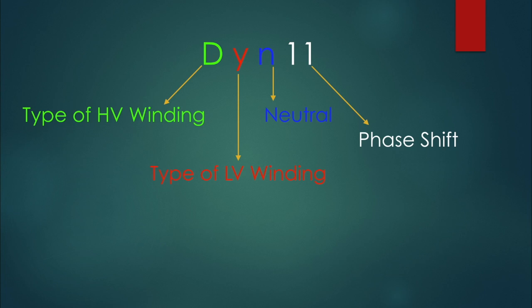D indicates delta connected primary winding. Y indicates star connected secondary winding with neutral point and 11 indicates the phase shift. So 11 is equivalent to 30 degrees. But the question comes how 11 is equivalent to 30 degrees. So let's find that out.